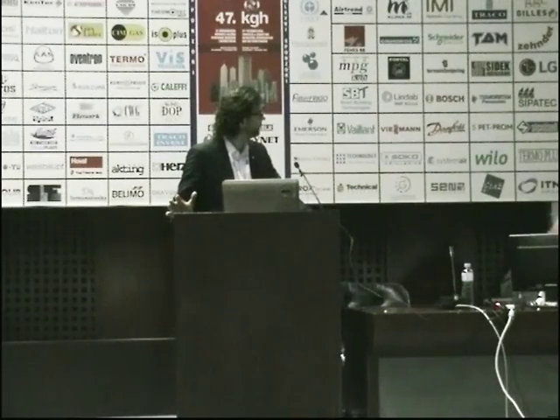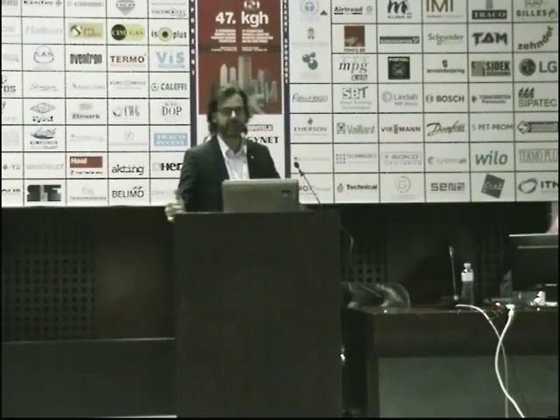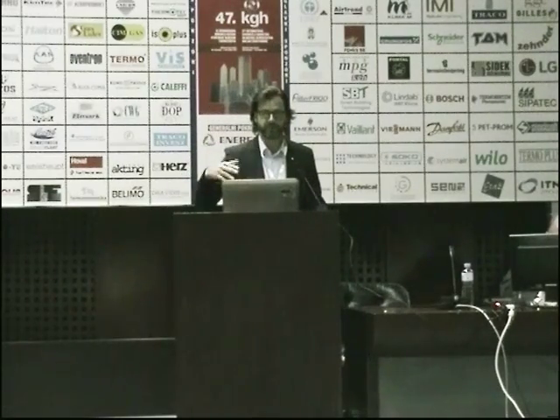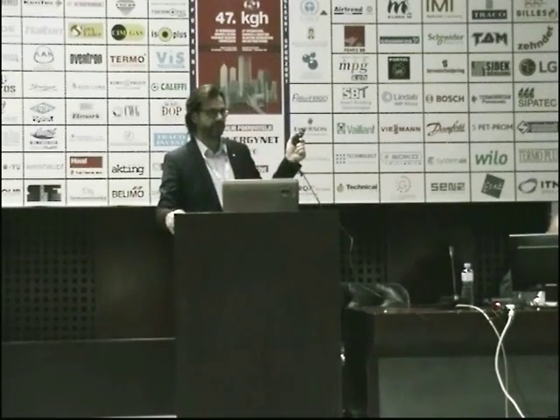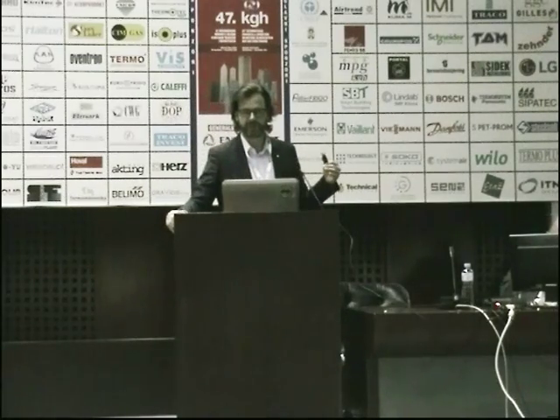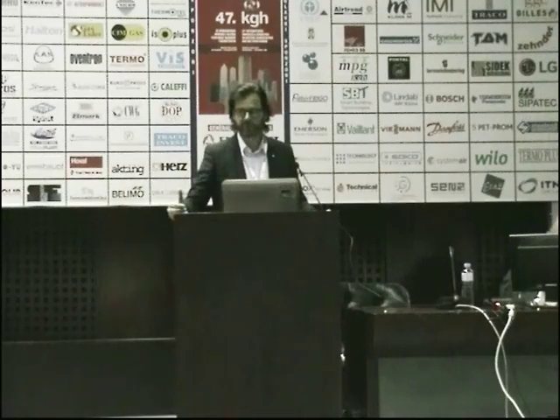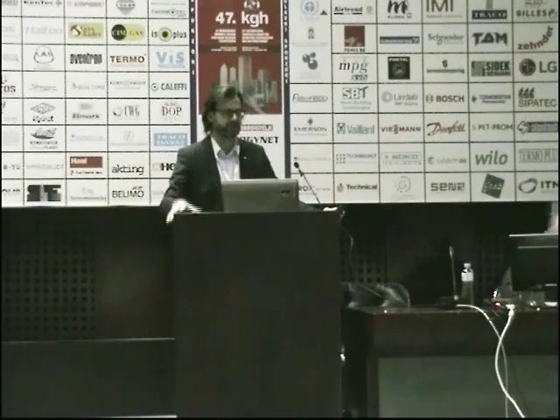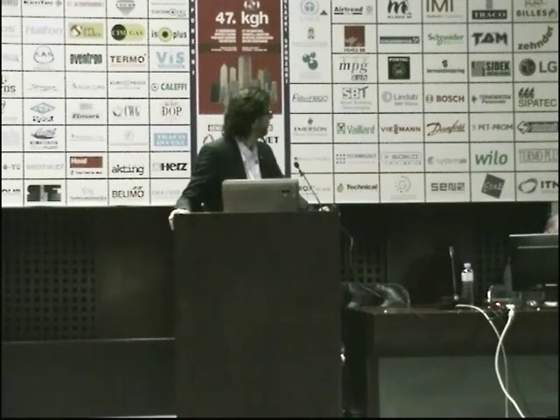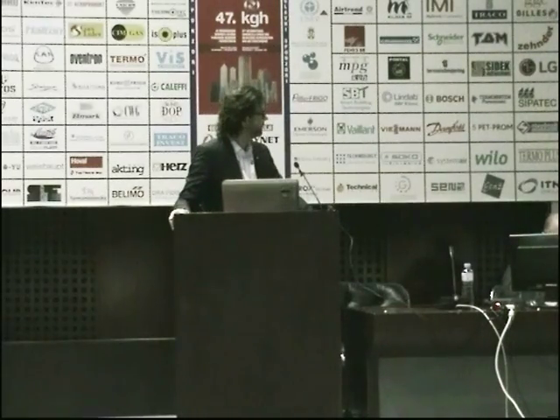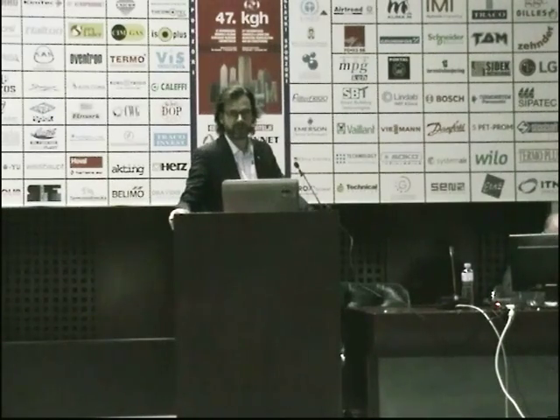First, as I said, installing the new systems while the supermarkets were open. Then installing the systems after changing the machine rooms. We changed the positioning of the machine rooms 3 times. In Cape Town, the ammonia machine room is at a height of 6 meters, and on the other side we have a school and kindergarten, so we had to take care of it. Then we had to check the shelves and cabinets with respect to CO2, also with respect to glycol defrosting and energy efficiency, so we did a lot of work for the cabinet producer.